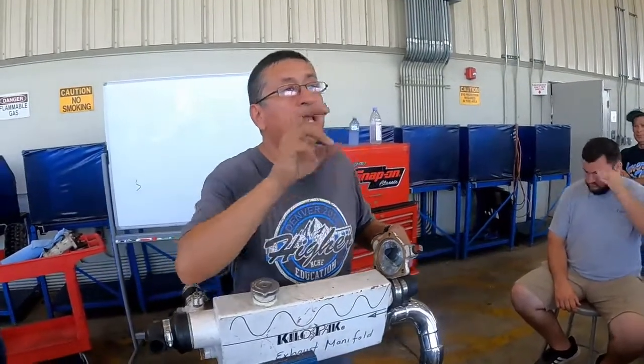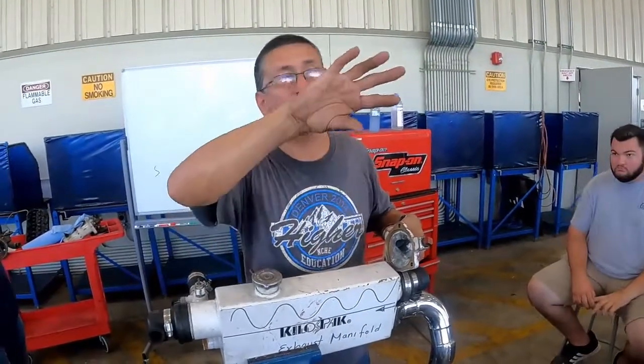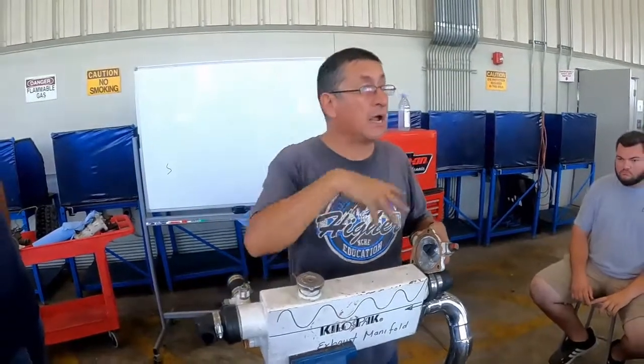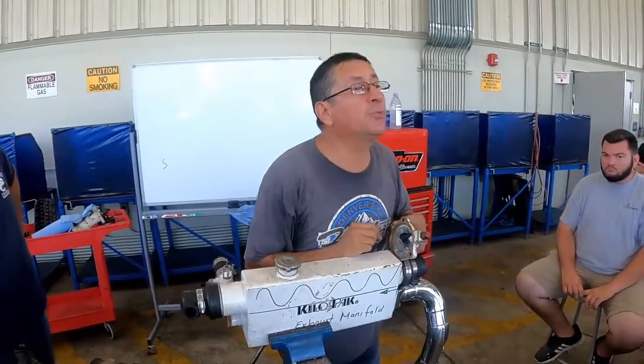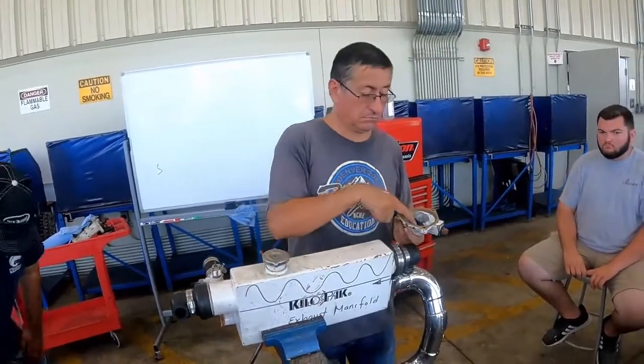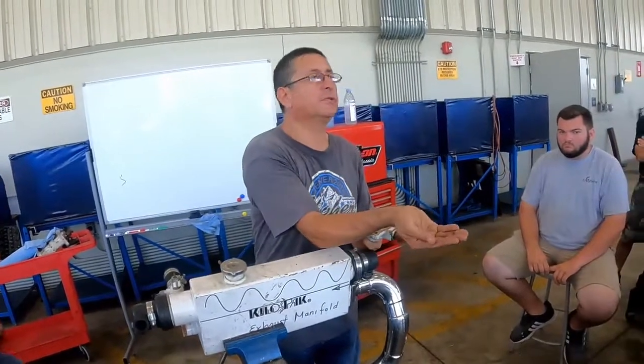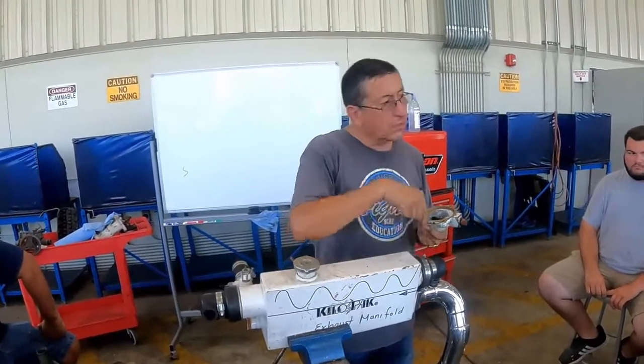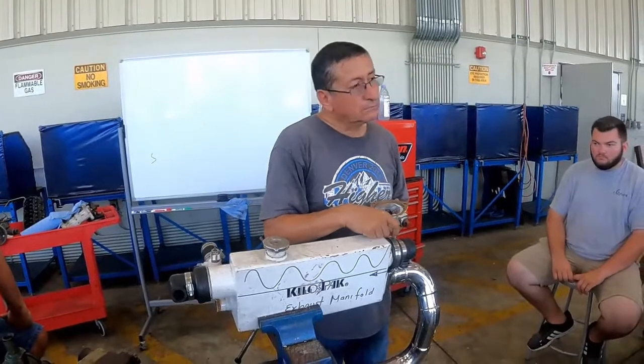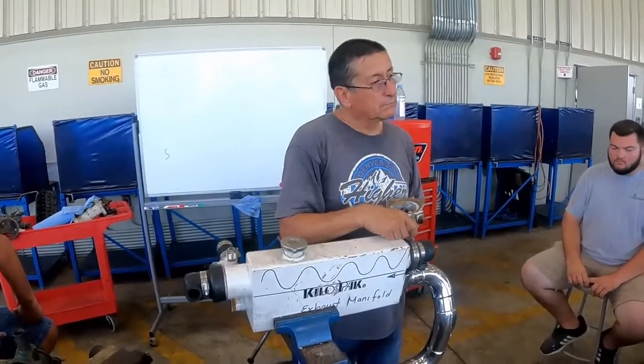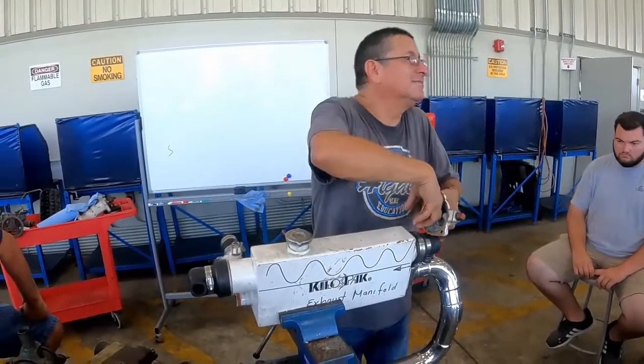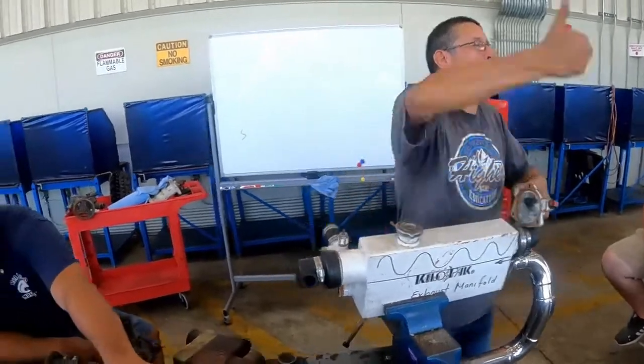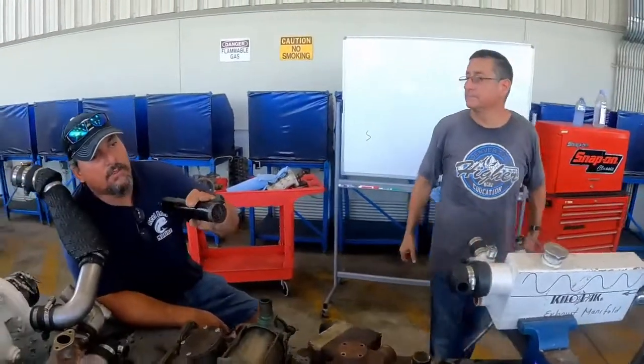Pay attention. I replaced the impeller, like Danny said, and I found that the impeller only had two blades. The other five blades are gone. Where are those pieces of blades? Right there, look, those are the pieces. They're going to go to the heat exchanger most of the time, or the cooler, depending on the pressure and the temperature. It's hard for those pieces to get through these.